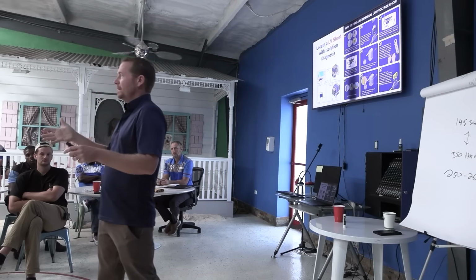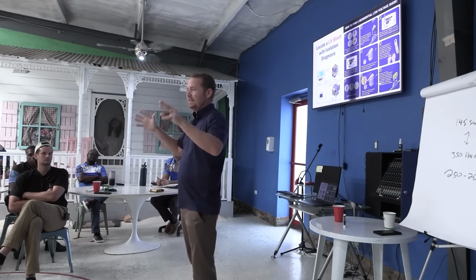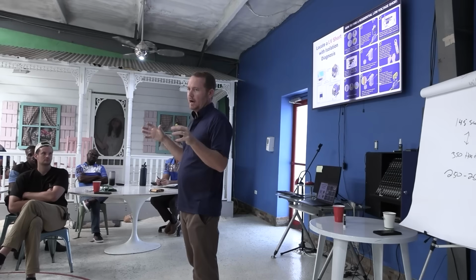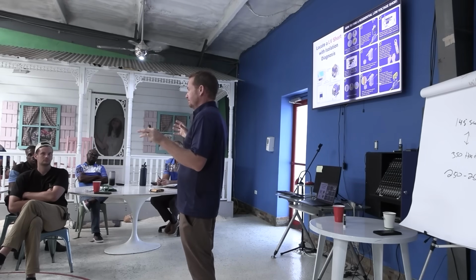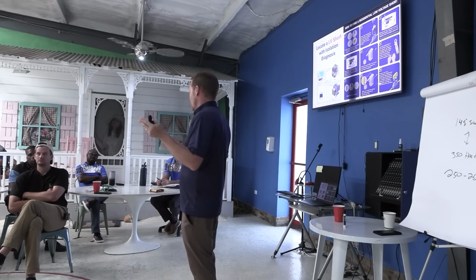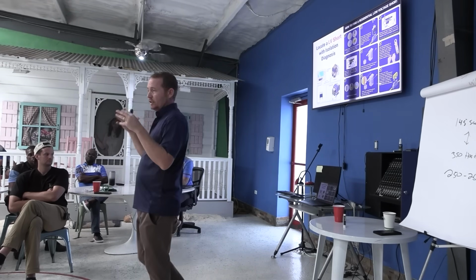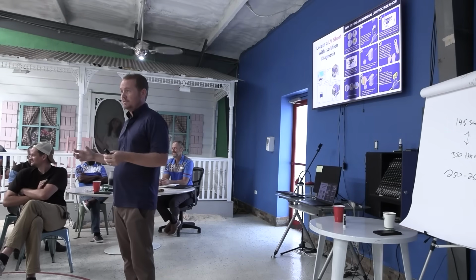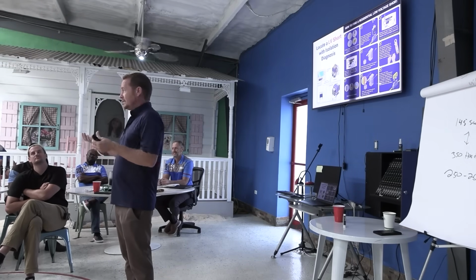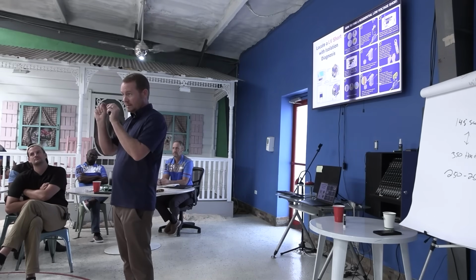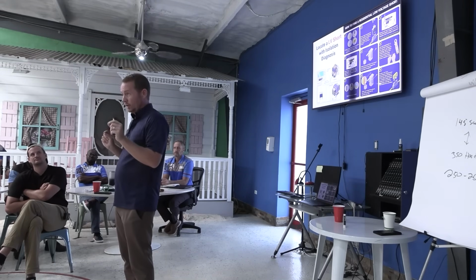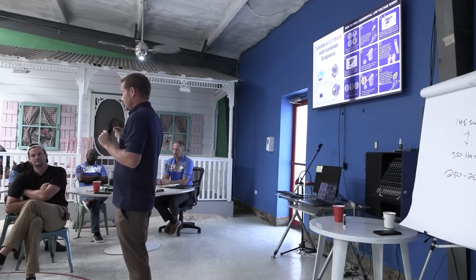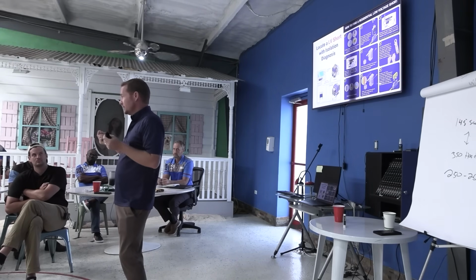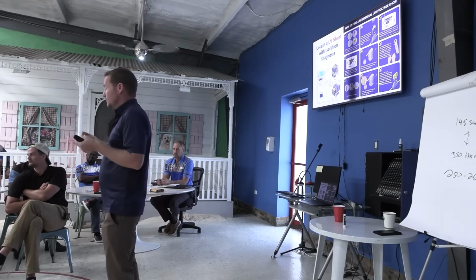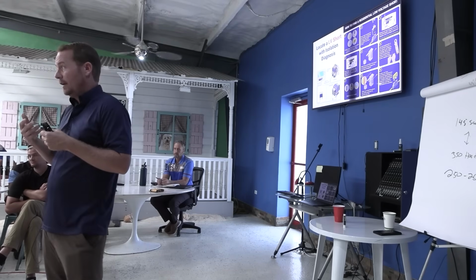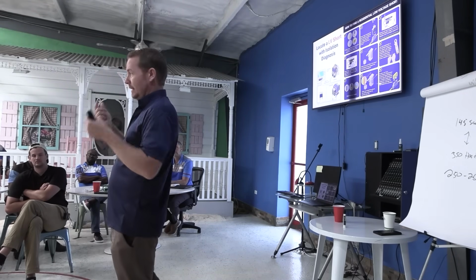So right now, in this room, what thing has probably the lowest operating resistance? Ice machine compressor, probably. The ice machine compressor probably has the lowest operational winding resistance right now. Have you ever ohmed out compressor windings on a working compressor? It's low, in most cases like 3 ohms, 1.5 ohms, 4 ohms, in that range. That's not very high ohms.